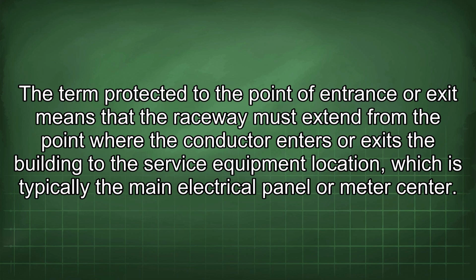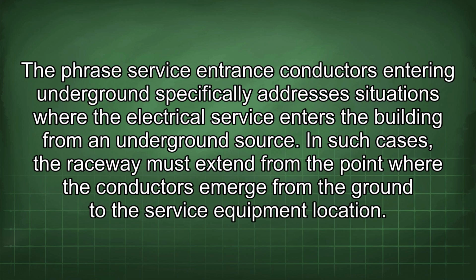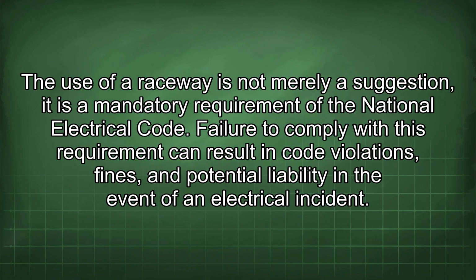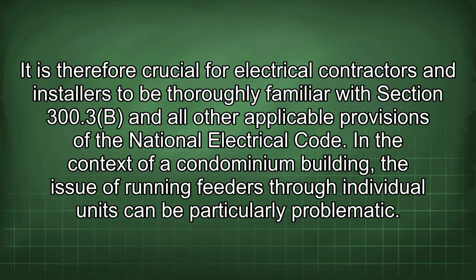The phrase service entrance conductors entering underground specifically addresses situations where the electrical service enters the building from an underground source. In such cases, the raceway must extend from the point where the conductors emerge from the ground to the service equipment location. The use of a raceway is not merely a suggestion, it is a mandatory requirement of the National Electrical Code. Failure to comply with this requirement can result in code violations, fines, and potential liability in the event of an electrical incident. It is therefore crucial for electrical contractors and installers to be thoroughly familiar with Section 300.3b and all other applicable provisions of the National Electrical Code.